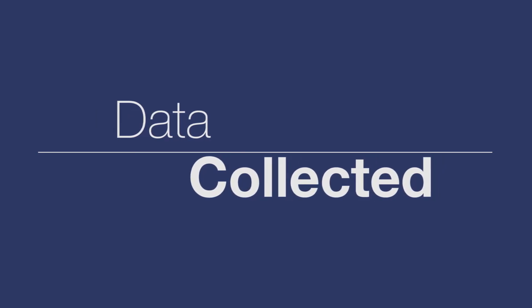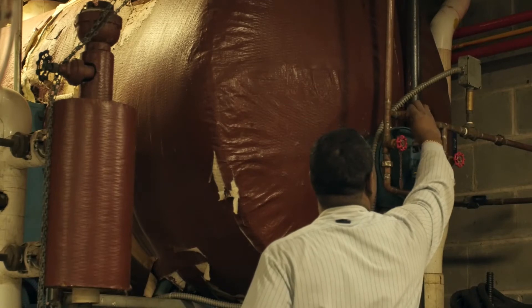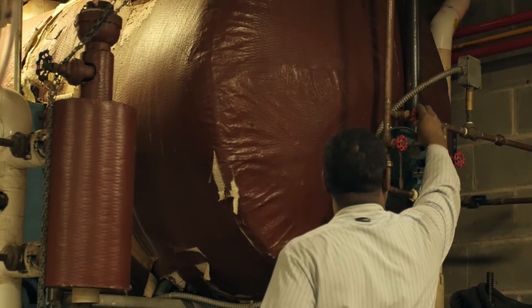So we did a quick survey. We found that there are about 600 to 650 steam traps in the building — mostly thermostatic cage elements and some F&Ts, about 30 F&Ts. The rest were all thermostatic cage traps. So we started a systematic process, starting at the top of the building and working our way down daily until we got all the traps done.